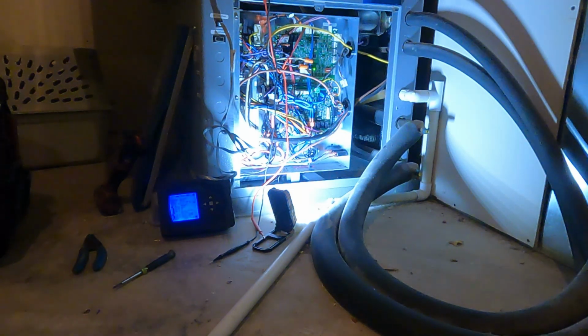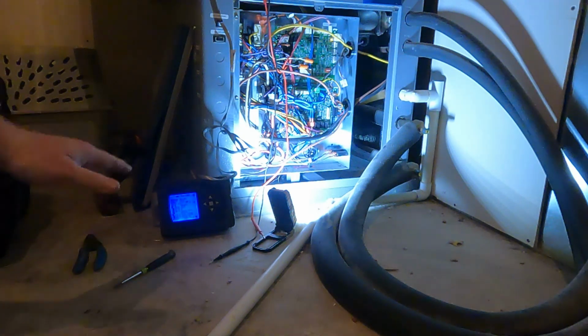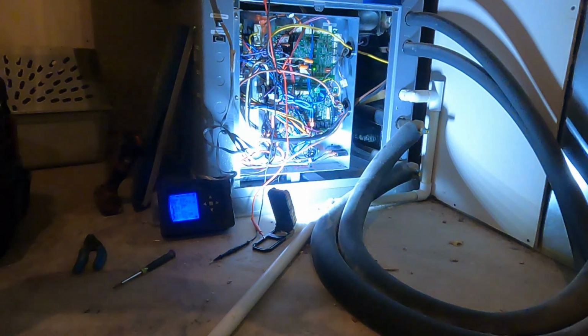On this particular model unit, I can look at the amp draws, I can look at the water pressures, I can look at the refrigerant pressures, all on this AID tool. It has to do with what features came with this WaterFurnace. So I'm going to go through there, check everything out, make sure the water pressure is good since it is a closed loop system. Make sure that the amp draws on everything are good. I'll probably go ahead and test the emergency heat while I'm here, just because we're getting into some colder months. But so far it looks like that's the issue.